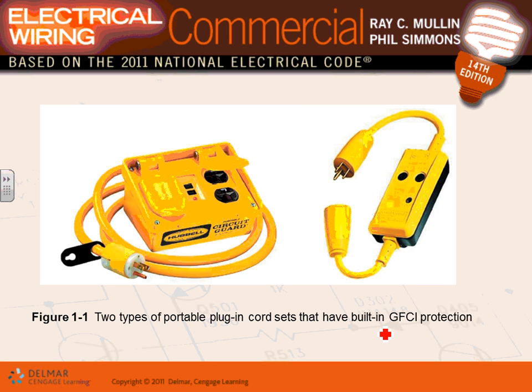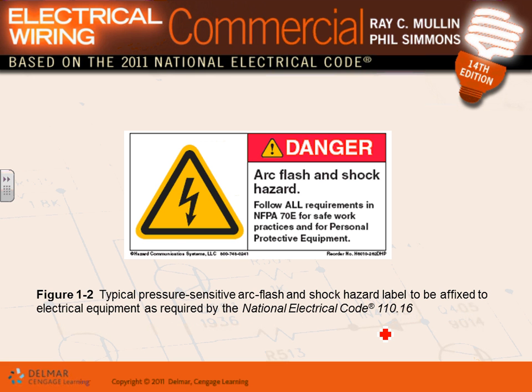When you're working in the field, these will be the tools that you're going to be using. Obviously, everything is GFCI protected. 15, 20, and 30 amps, 120 and 240, 120 in the field have to be GFCI. Every panel, based on any NEC code book, guys, has to have a label that warns people of the arc flash hazard and the shock hazard too, and it will have a category from 0 all the way to 4, 4 being the worst arc flash you can encounter.